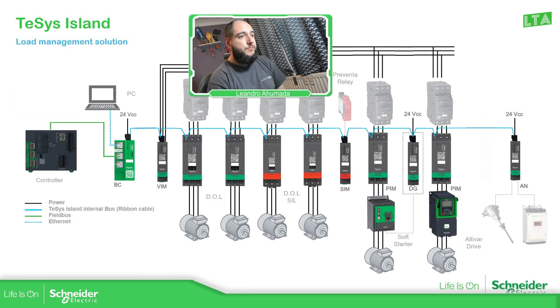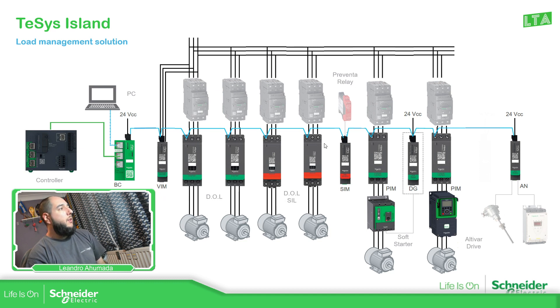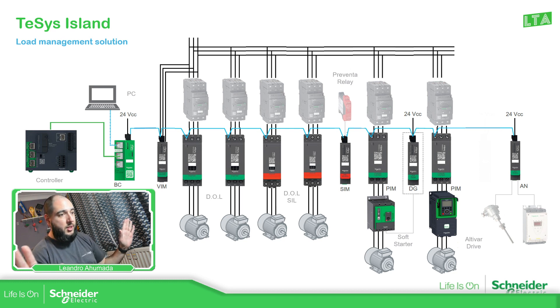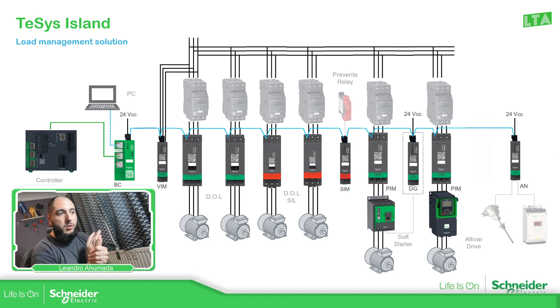Here is a picture showing the different alternatives using different modules for the TeSys Island. At the beginning we have the bus coupler communicating with a PLC — in this case an M262, but it can be any PLC that talks over Modbus TCP, EtherNet/IP, PROFINET, or PROFIBUS. Then we have the voltage interface, which is connected to the motor supply and measures the complete island. If we have different motors using just one voltage interface module, it will cover them all. Then we have the starters.